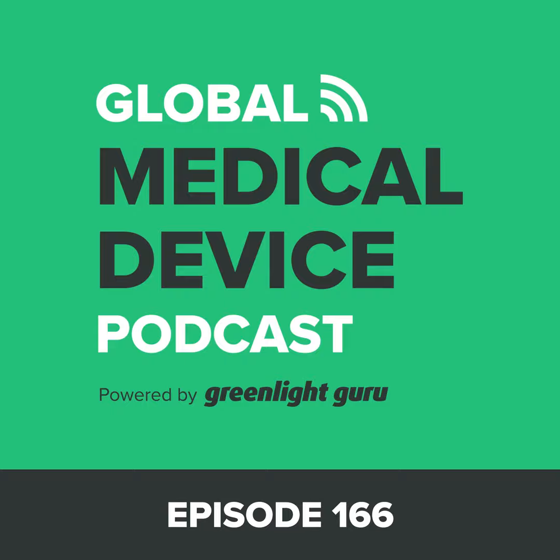It's one thing to say my device is going to be used in contact with the skin. It's another thing to talk about, say, a subcutaneous implant, maybe something in contact with the bone. It's a third thing to say a cardiovascular implant, maybe a stent that's going to be in contact with the blood. We can't treat all of those similarly.